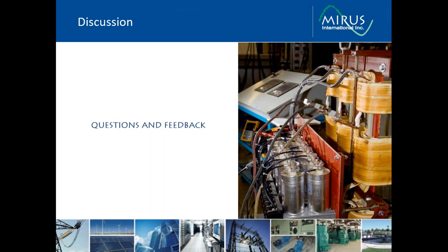Okay, just got a new question, maybe a follow-up to the previous one, about the impact of the DC bus capacitance. Does capacitance of the DC bus, higher or lower, have any impact on the input harmonics? Yes, certainly. The different DC bus capacitance will result in different harmonics being drawn by the rectifier. Same spectrum, 5th, 7th, 11th, 13th, and so on, but you can get much higher levels if you have less DC bus capacitance. So that can be a concern.